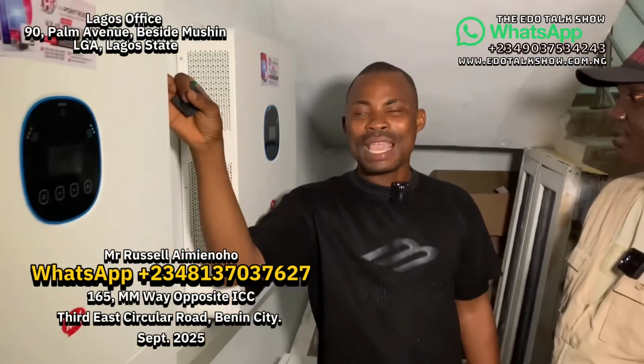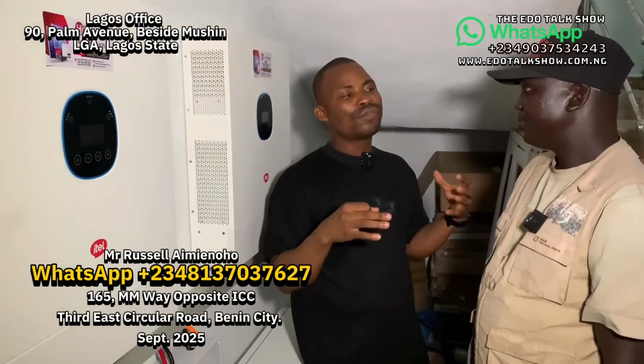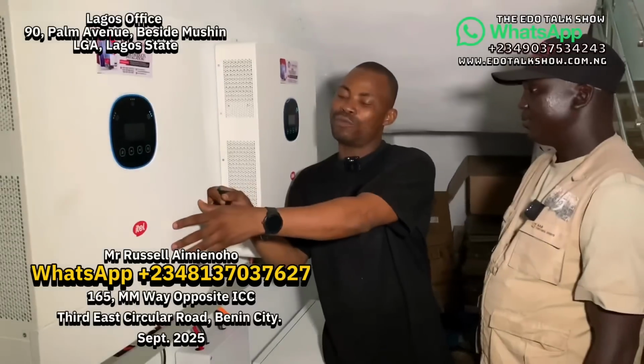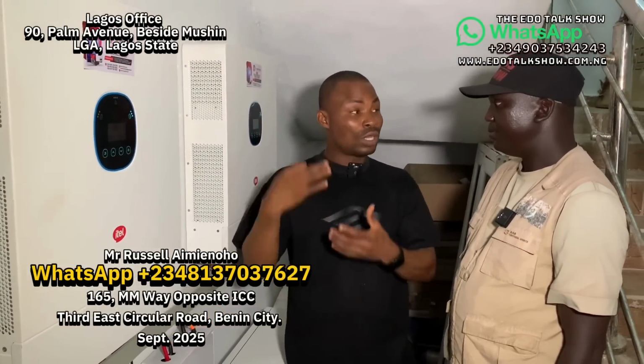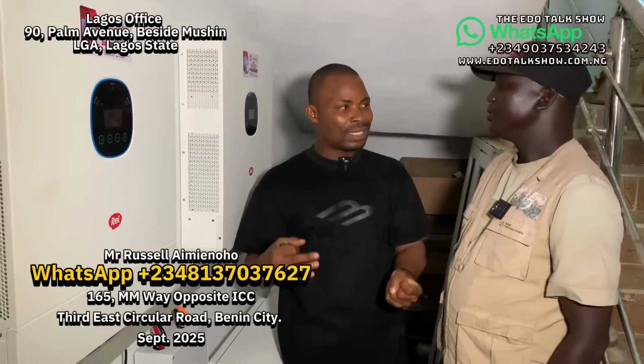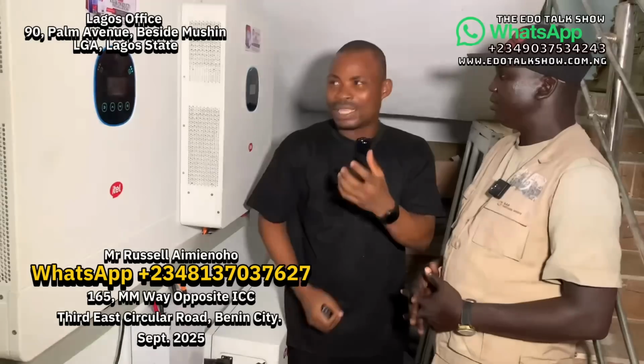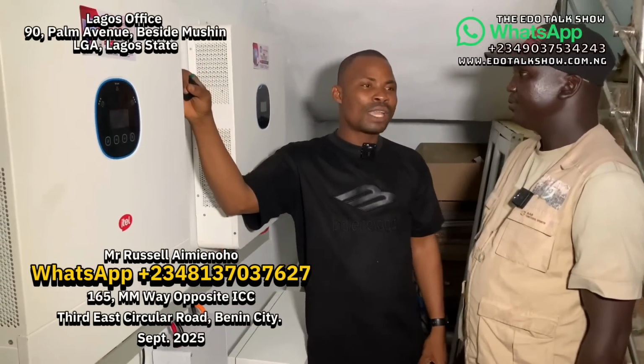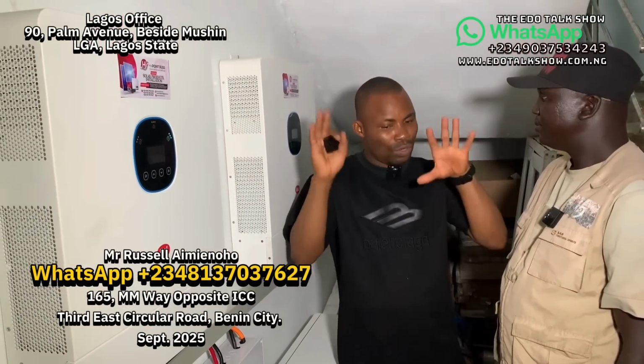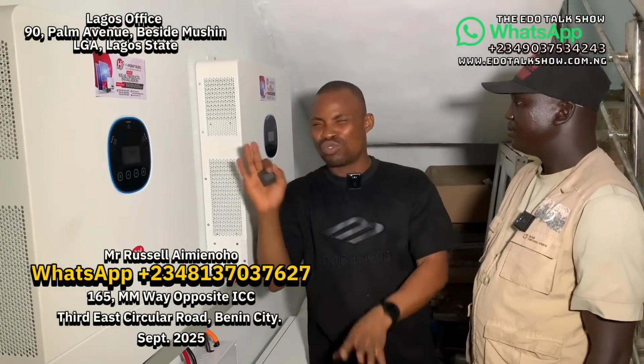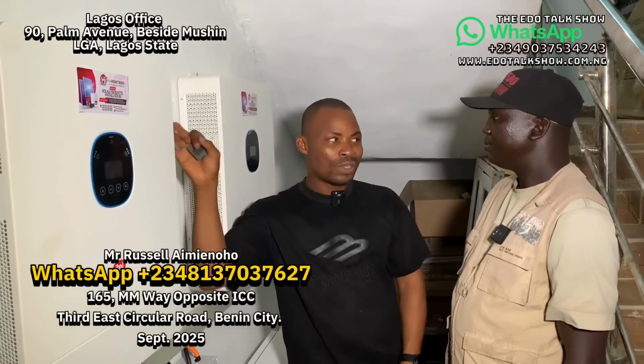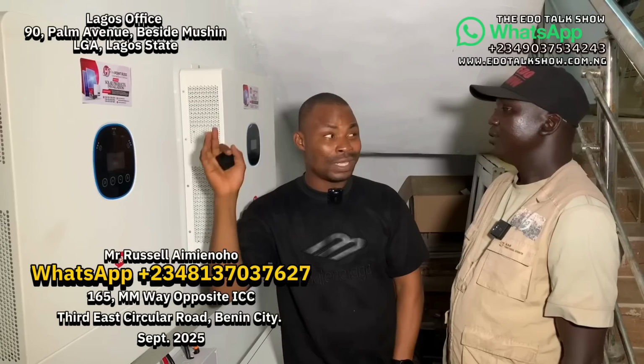But usually this is a 14 kVA inverter. For that 24 kVA, that means if you pull a load of 20 kVA on top of this 14 kVA inverter, for a start, like all those inductive loads, they need enough energy to start. So this inverter will give 24 kVA for them to start. Then when the load becomes stable, it returns to normal. That's why it's called surge starting current.